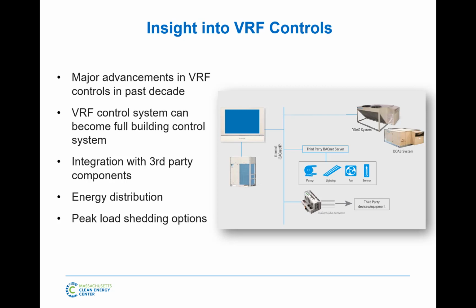If you have a single split, that condensing unit on the balcony or on the roof is going to be wired to the panel in the suite right there, and that panel is already sub-metered by National Grid or Eversource or whoever you might have. Now I've got one machine on the roof serving 10 suites. Who pays for what? In my mind, I think that's been one of the biggest hurdles, especially in states like Massachusetts, to do that. I'll explain why.